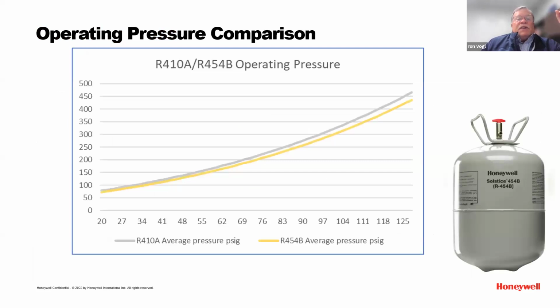A lot of people ask about this in air conditioning. How different is 454B going to be to 410? So I just plotted the average operating pressures across the whole temperature range, and you can see that they're very similar. 454B having a slightly lower operating pressure, not by much, but it will not be a lot different servicing this from a pressure, superheat, subcooling standpoint. Your gauges will be, you'll be familiar with the equipment if you had familiarity with 410A.